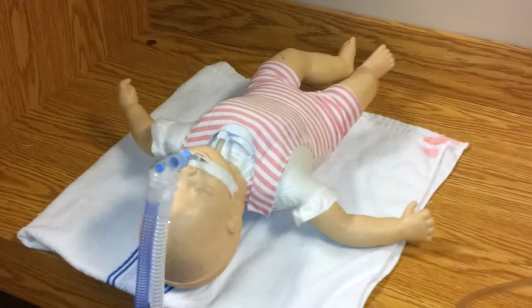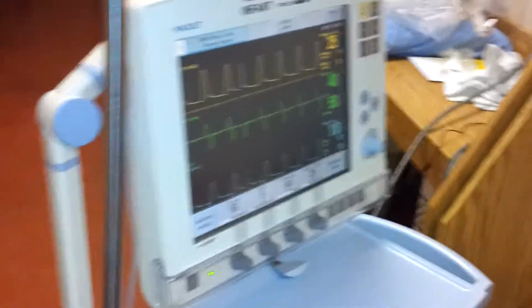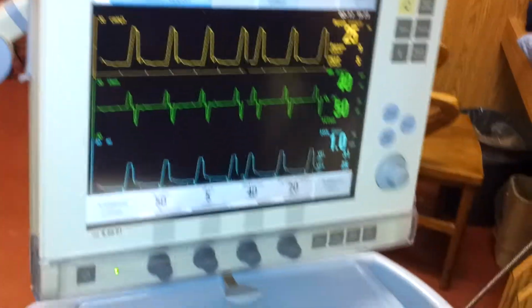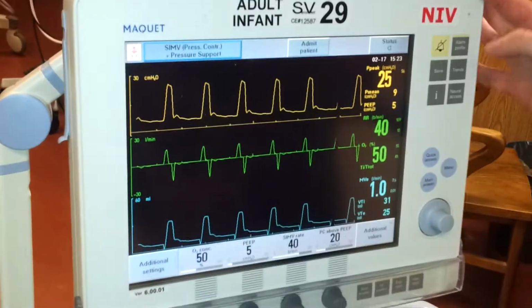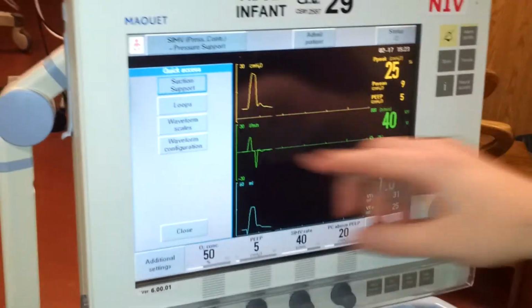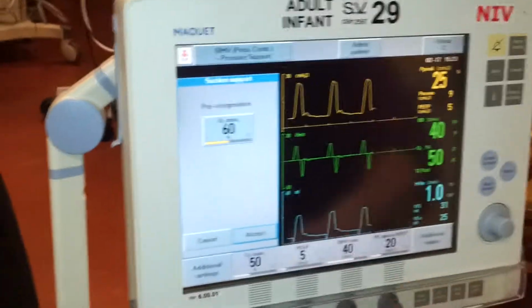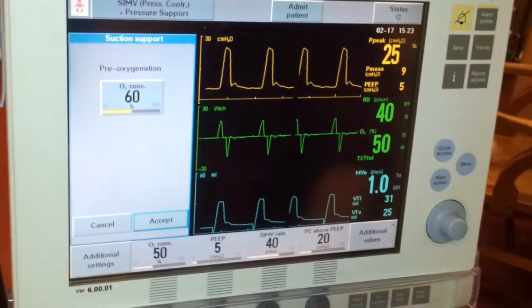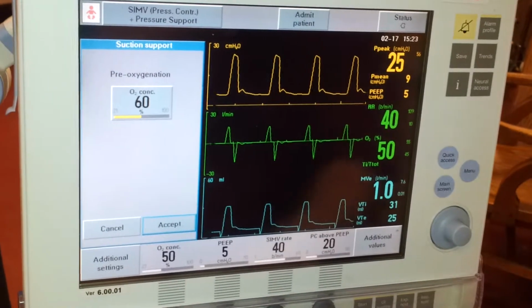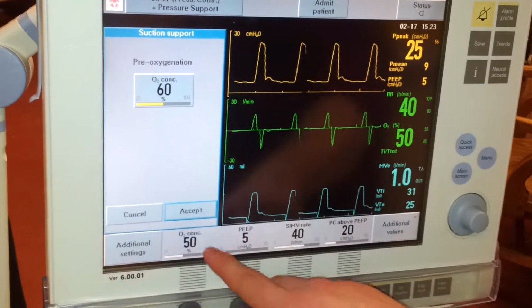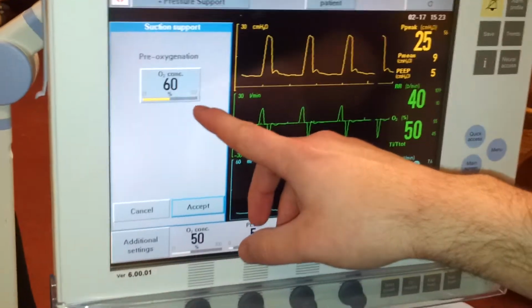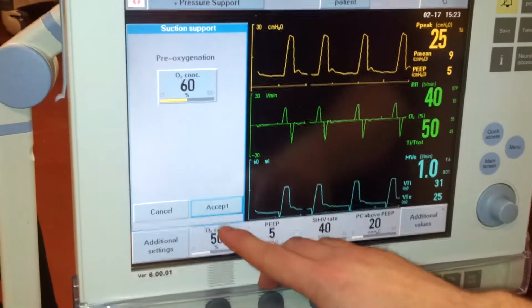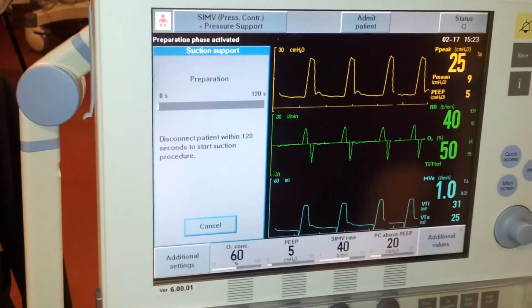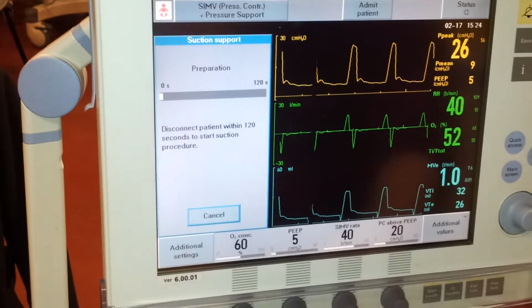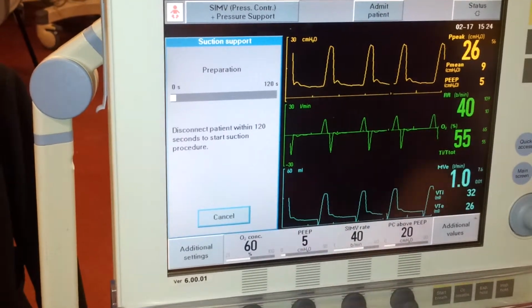Step 3 is pre-oxygenation. On the Servo-I, it has a feature called suction support, which makes it really easy to suction. So you go to quick access, suction support, and for the neonatal population, you want to increase your FiO2 by 10 to 20%. So if they were set on 50 before, you would change it to 60 for pre-oxygenation. So hit accept, and now it will give 120 seconds of that selected FiO2, which was 60%.